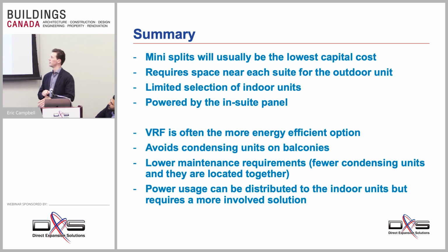And lastly, as I just mentioned, it's powered by the in-suite panel as long as it's close by, which has savings in terms of the electrical infrastructure. For the VRF side, VRF is often the most energy efficient option. Again, the reason for that is that you've got so many more indoor units served by one outdoor unit. So that outdoor unit can run most efficiently as continuously as possible, sharing the load of all the indoor units among one optimized compressor.